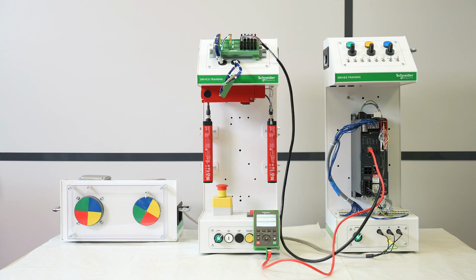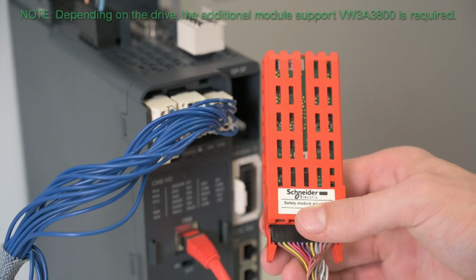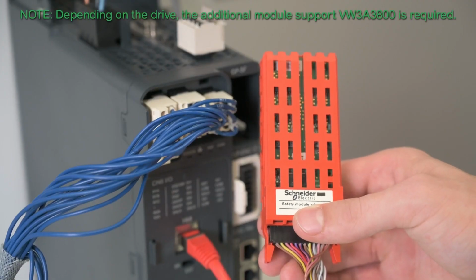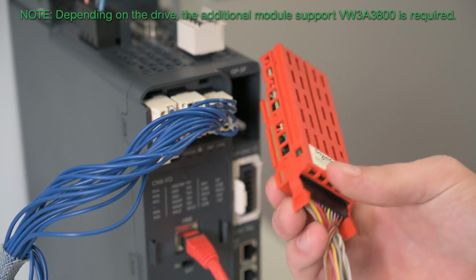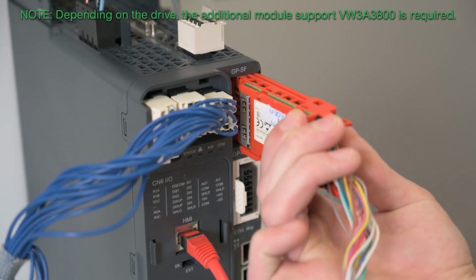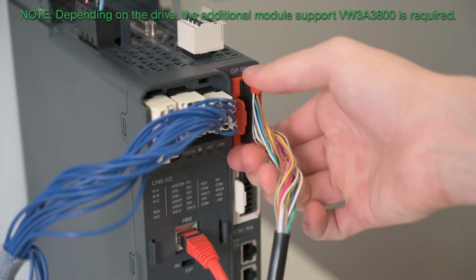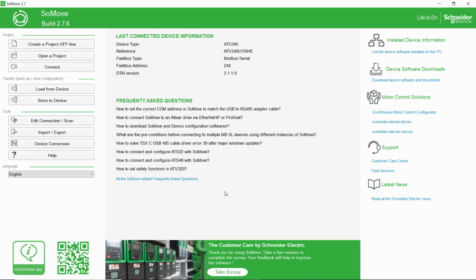Configure the motor and encoder parameters for the safety module VW3A3802. After the installation of the safety module inside the drive, but also the installation of the other required options, such as the encoder module, connect with SoMove to the drive. Once connected to the drive, verify the topology of the drive.